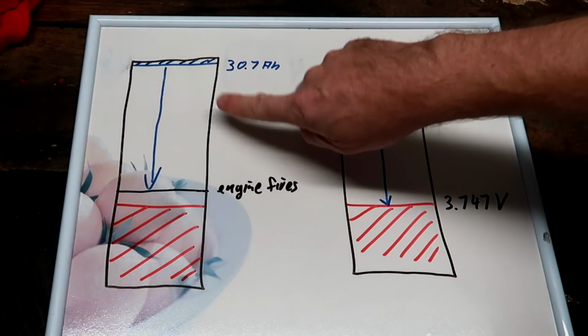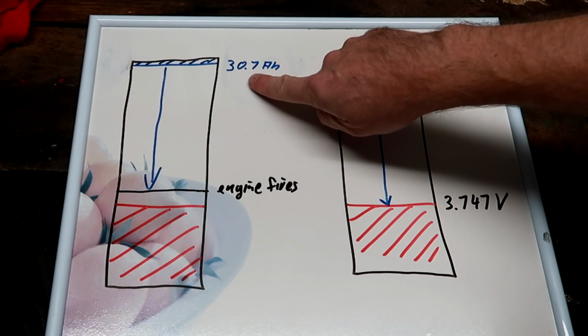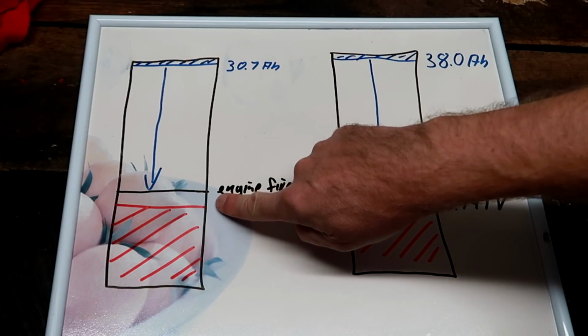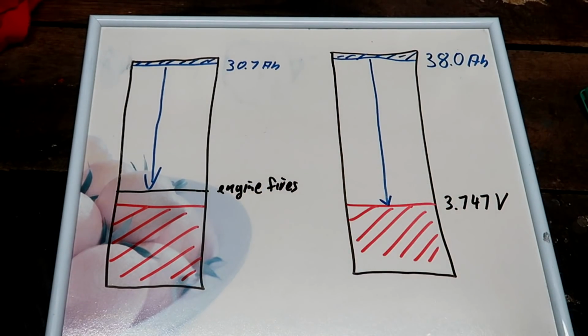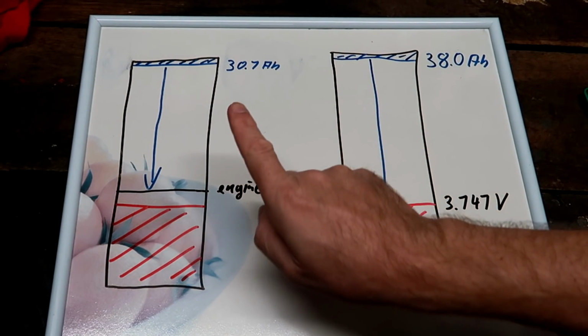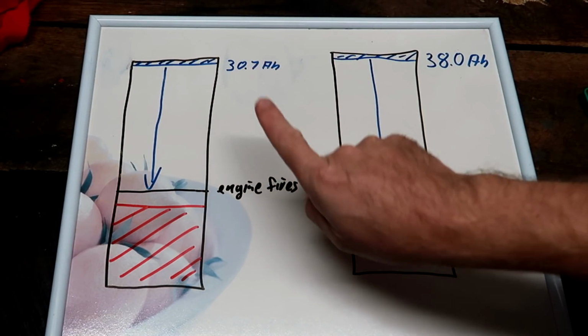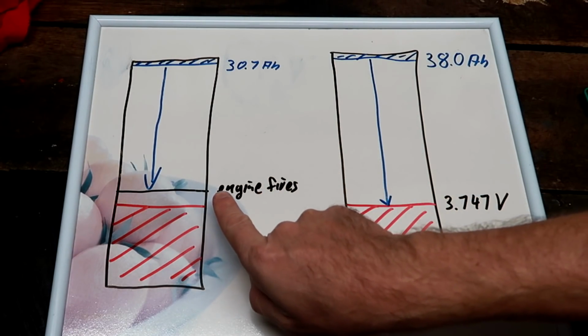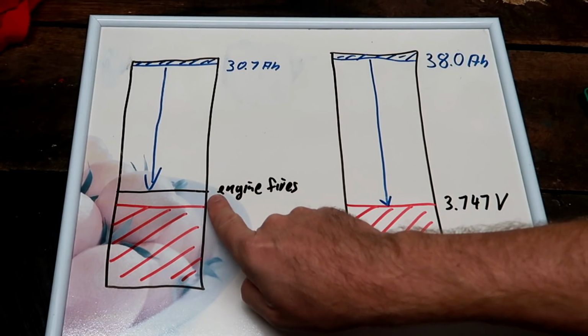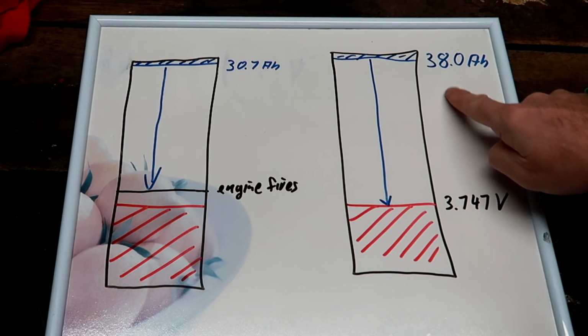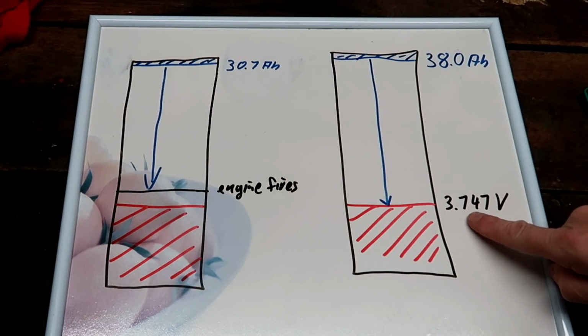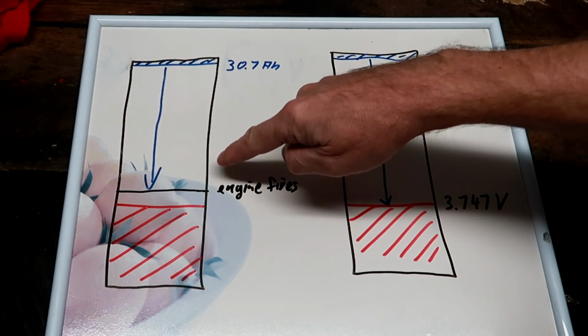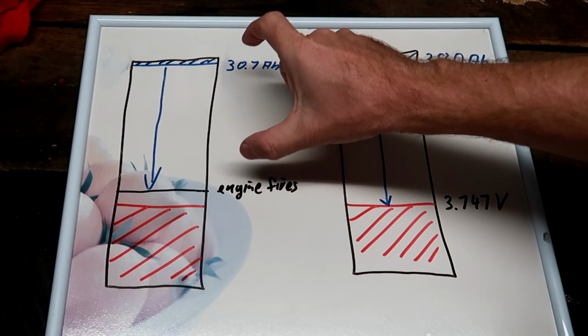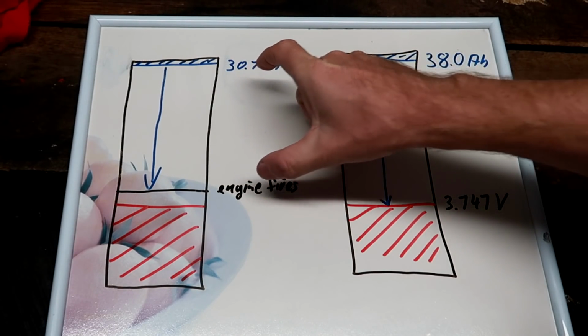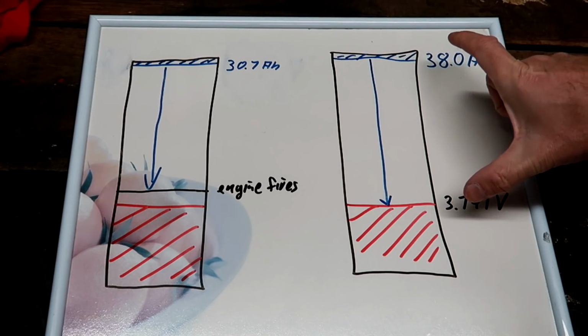If we do the same with the same battery, but the BMU thinks it has less capacity, what is the voltage then when the engine fires? So the theory behind it is: if the BMU limits the capacity of the battery, it fires the engine at a higher voltage than with the correct calibration. In this case we know it's 3.75 volts, but with less capacity assumed, it might be higher, maybe 3.8 volts. So it doesn't use the full capacity of the battery, while in the correctly calibrated case, it does.